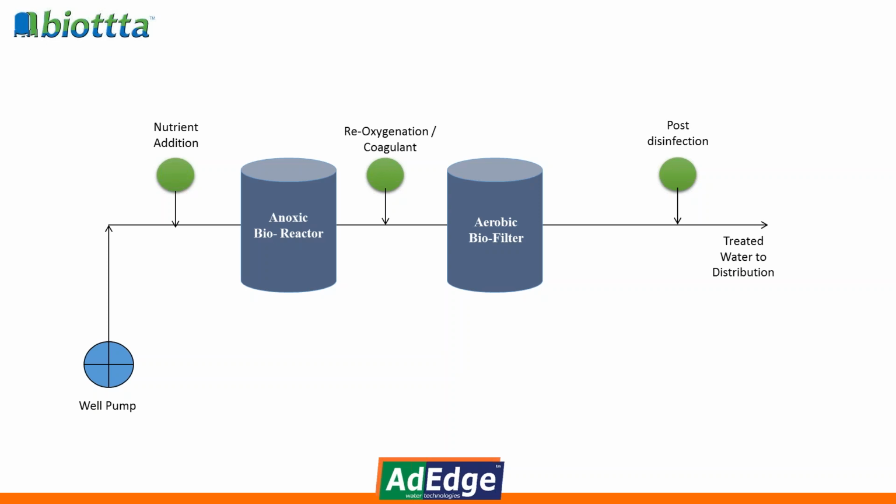What's going to happen in the aerobic biofilter then, it will convert into an aerobic bed. You will get some final clarification within this filter. We also have a sand layer of silica sand in here that will be used for filtration. So the coagulant in conjunction with the sand layer will allow the water to come out of the aerobic biofilter, meeting the 0.3 NTU discharge standard that was established by the state of California for all the biological testing going on over there.